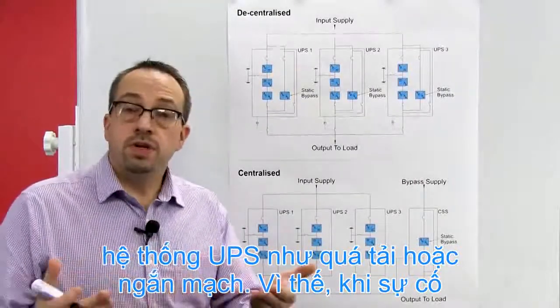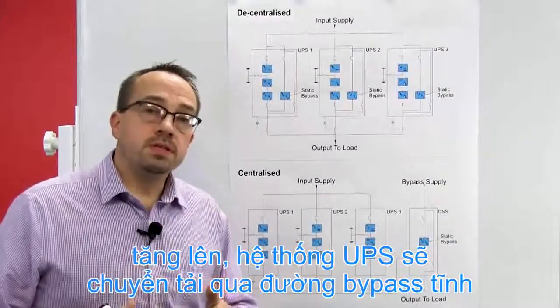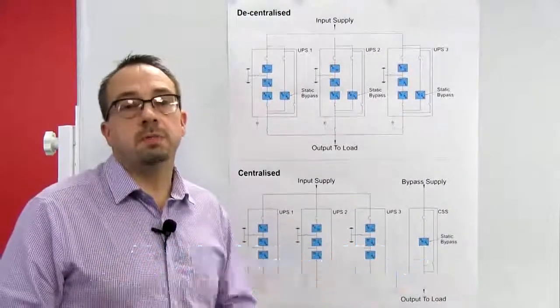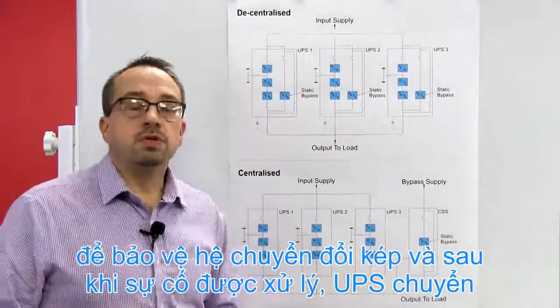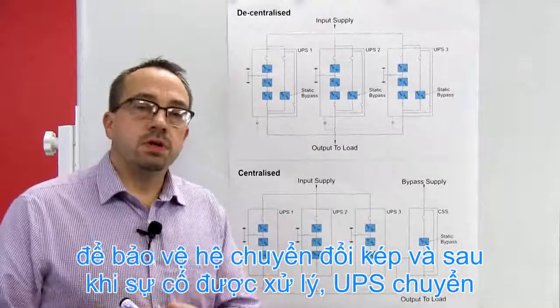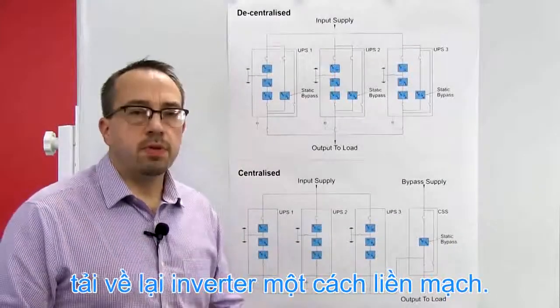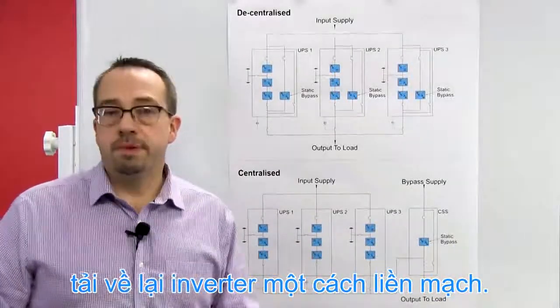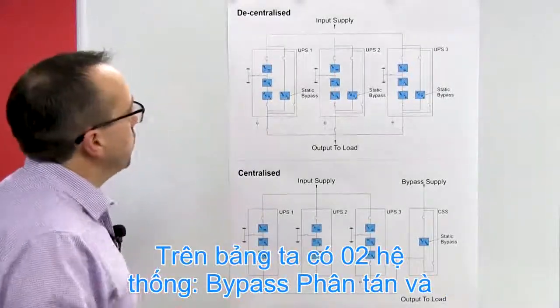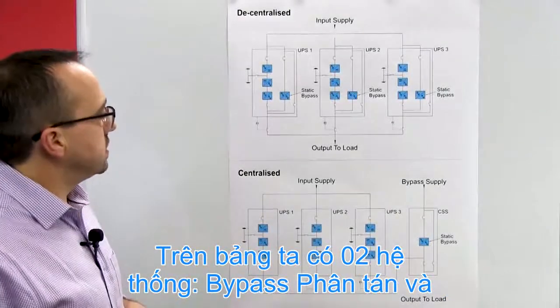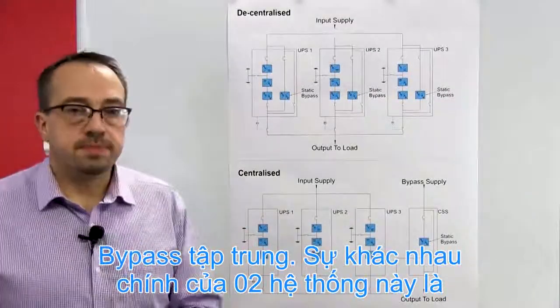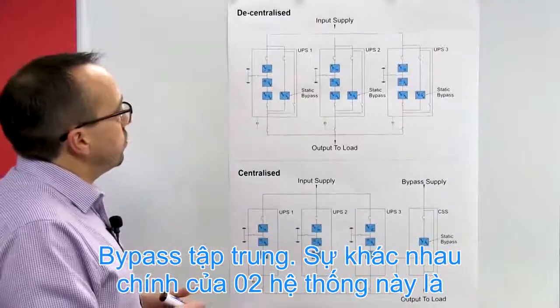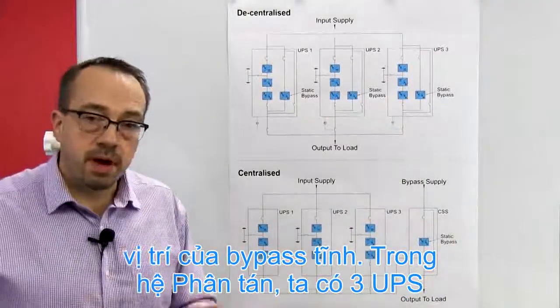And therefore, should an issue arise, the UPS system will simply transfer the load onto the static bypass, allow the issue to be resolved, and then once it's resolved, can transfer the load back onto the output of the inverter completely seamlessly. Now on the board here we have two systems. We've got the decentralized system and we've got the centralized system. Now the main difference between the two systems is the location of the static bypass.